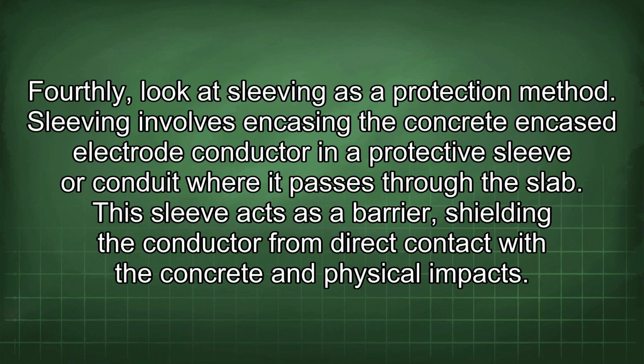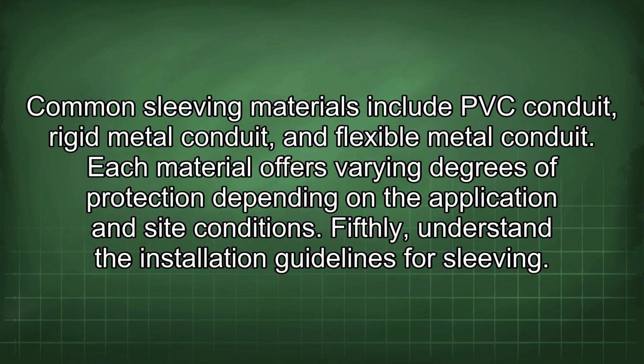Fourthly, look at sleeving as a protection method. Sleeving involves encasing the concrete encased electrode conductor in a protective sleeve or conduit where it passes through the slab. This sleeve acts as a barrier, shielding the conductor from direct contact with the concrete and physical impacts. Common sleeving materials include PVC conduit, rigid metal conduit, and flexible metal conduit. Each material offers varying degrees of protection depending on the application and site conditions.